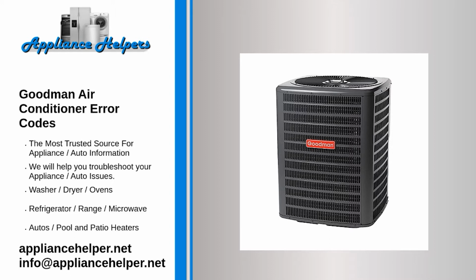Code A3, problem: shorted sensor, open sensor disconnected, sensor out of range. Code E5, problem: short in low voltage wiring. Code EE, problem: compressor relay contacts welded. Code B0, problem: indoor blower motor problem, communications error between indoor and outdoor unit. Code B9, problem: indoor blower motor problem, blocked filters, restrictive, undersized ductwork, indoor-outdoor unit mismatch.